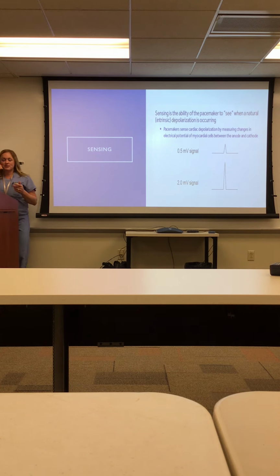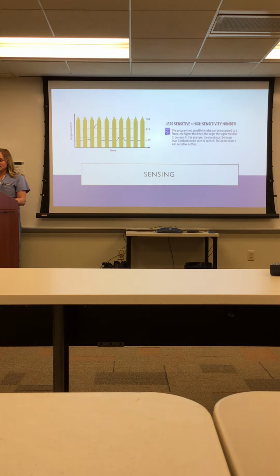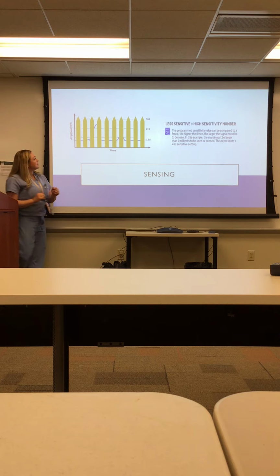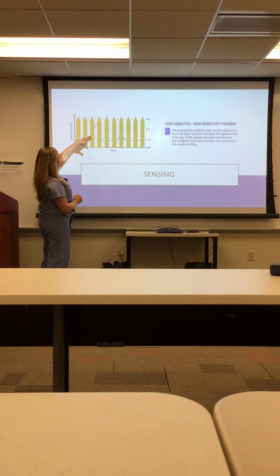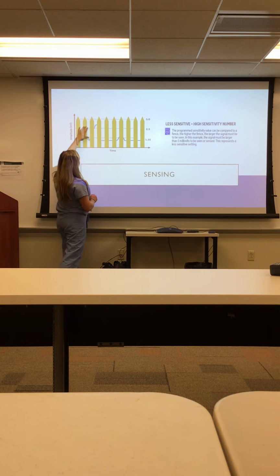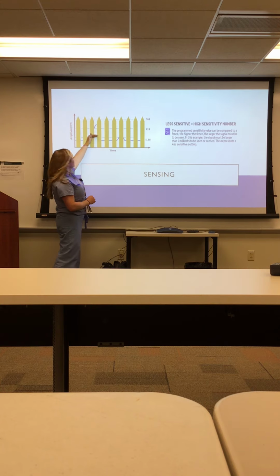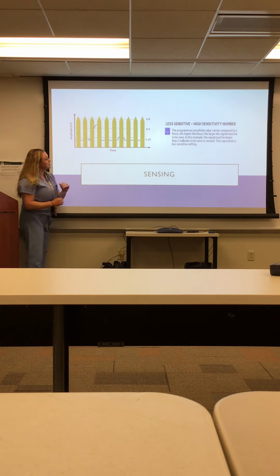It works kind of backwards because you want to go higher with your fence and higher with your value as far as sensing goes. But the higher the fence, the less sensitive it is, and the less it's going to see from the intrinsic beat that comes through. So we'll look at that here. The less sensitive, the higher the number, or the higher the fence. So if you see that 5, you've got your fence all the way up there, and any R waves that are coming through that you're trying to sense, you're not going to see anything. It's too high. So you've got to bring that fence down so you can get at least half of that signal in there.